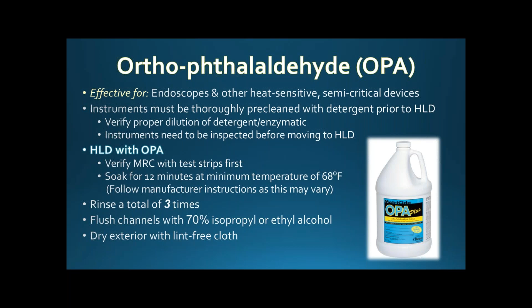The other part is that you have to make sure that you are taking the temperature of the solution. You need to make sure that the solution is at a minimum of 68 degrees Fahrenheit, and sometimes you might have to change the temperature of the room to be able to get up to that temperature. The other part is that it needs a total of 3 rinses, so you need to make sure that when you do observations you see those 3 rinses. And then if you're using something with a channel, you can always flush through those channels with 70% alcohol and then dry the exterior.